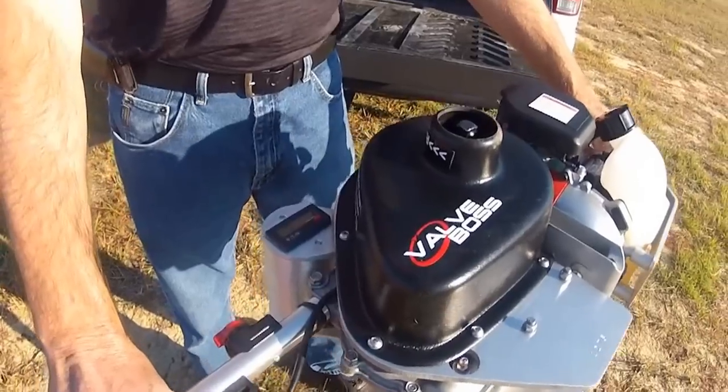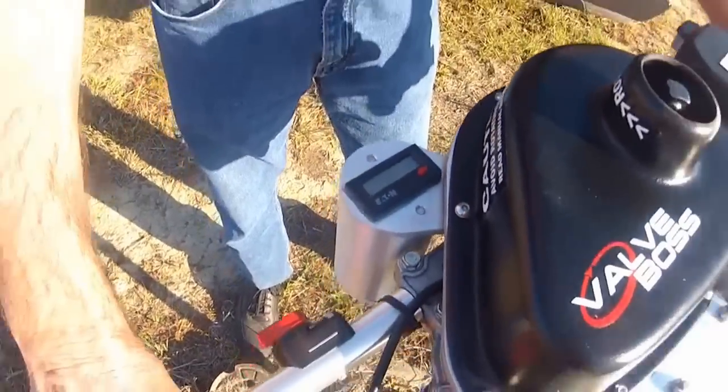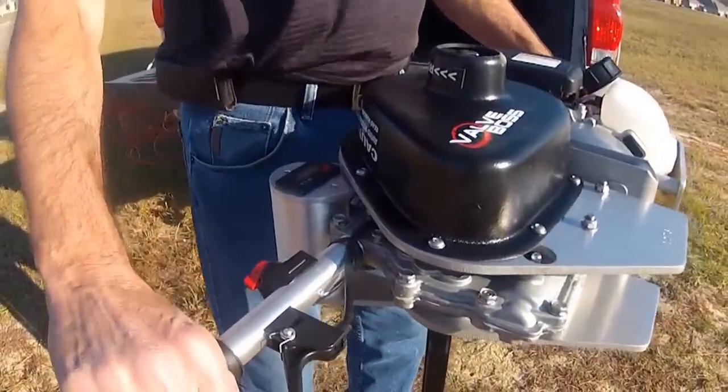You can see the numbers are coming up on the counter here. We're at 16, 17 turns. This is a six-inch valve. I'm going to start throttling back. I've got my 20 turns on it. The valve is fully closed.